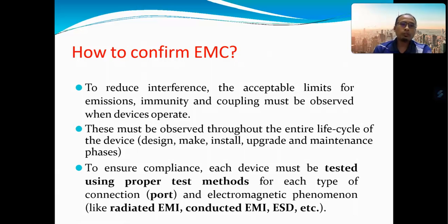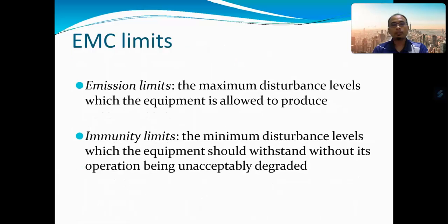So in order to ensure compliance to EMC for this device, the device must be tested using the proper test method for each type of connection and also each electromagnetic phenomenon. For example, radiated EMI, conducted EMI, or electrostatic discharge test, and so on.